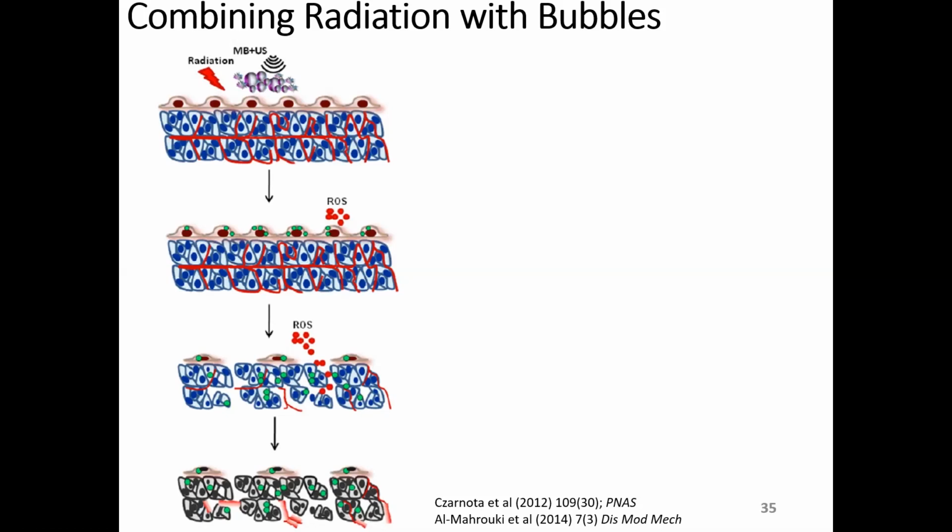Now, the ultrasound itself, without the presence of bubbles, there are frequencies and pressures, mostly pressures, which actually will cause irreversible damages to tissues. I'm talking right now about approaches such as high-intensity focused ultrasound or histotripsy approaches that actually, with the pressures of the sound waves, will damage the tissue. That is not what we're doing here. So our pressures are selected in such a way that they're only meant to burst these bubbles and not cause irreversible damage to the surrounding tissues.